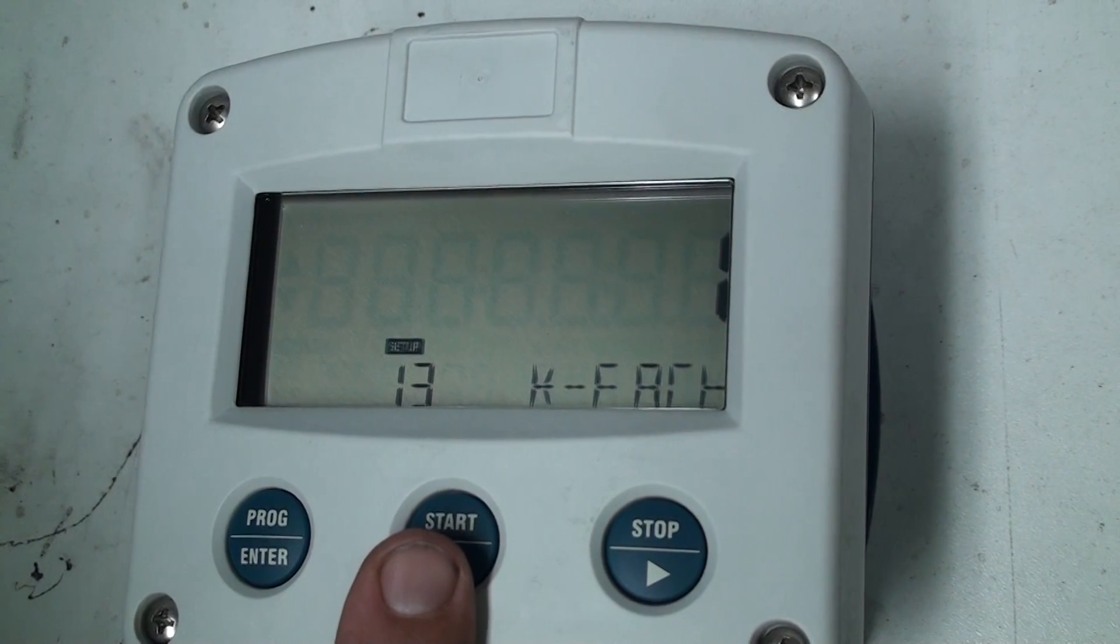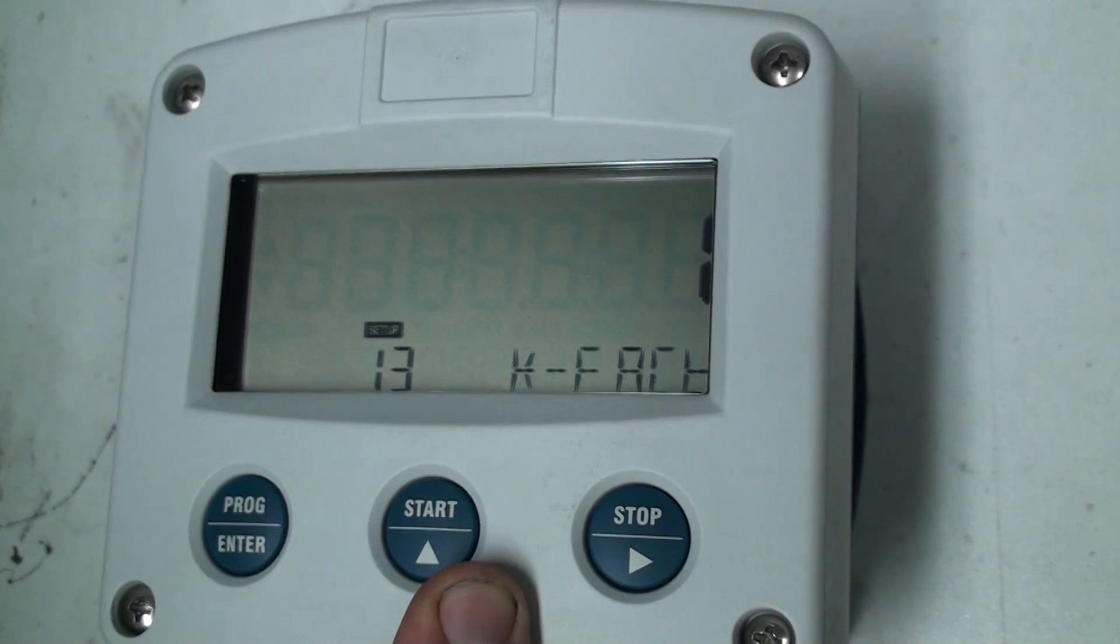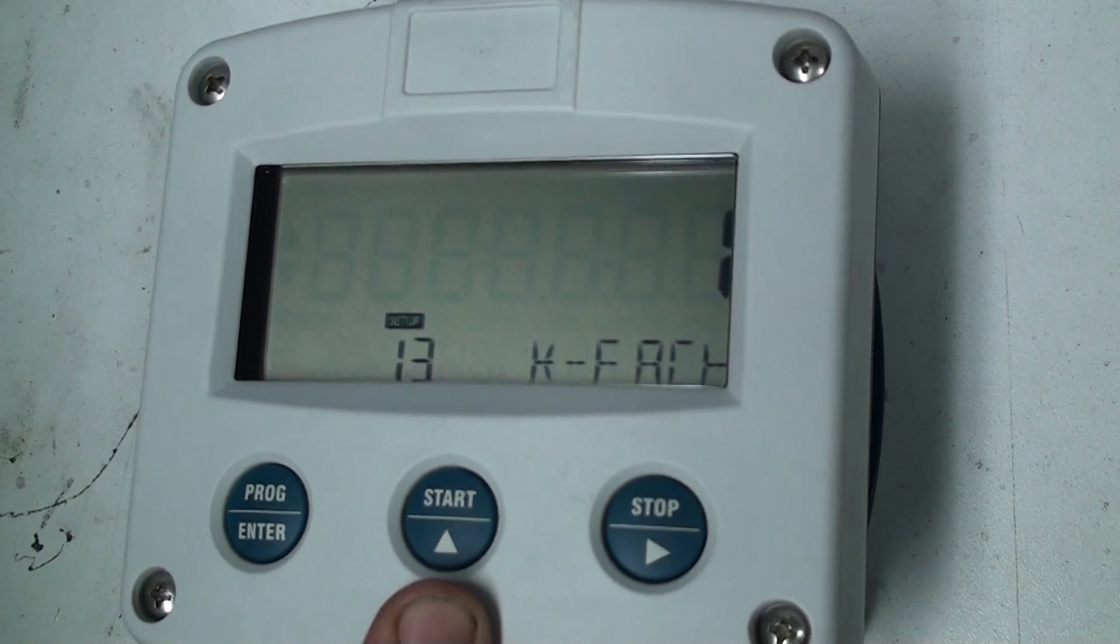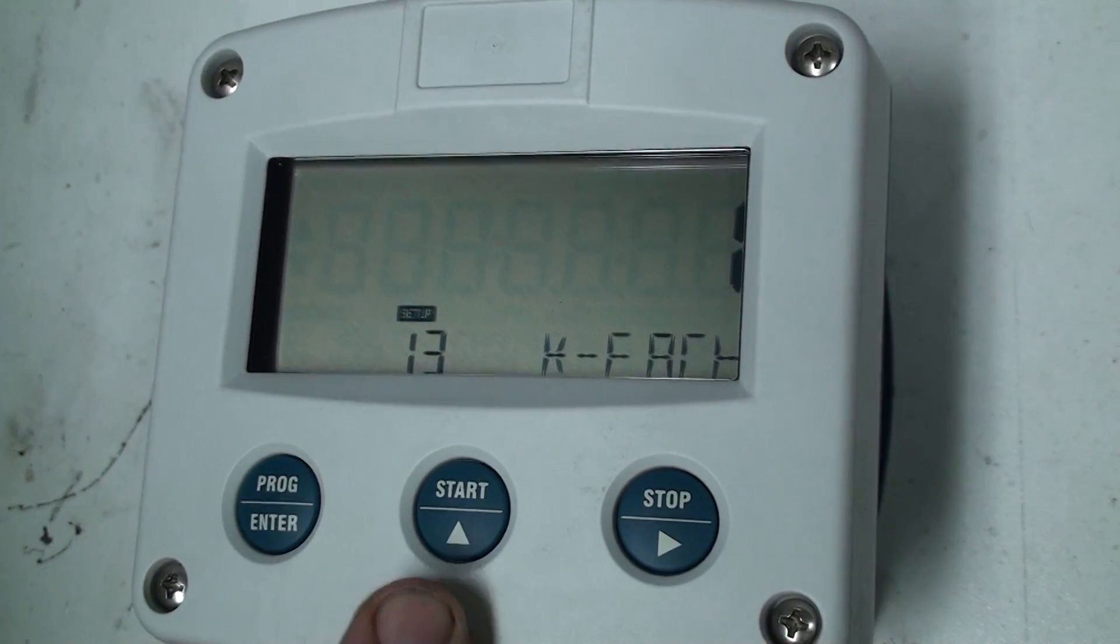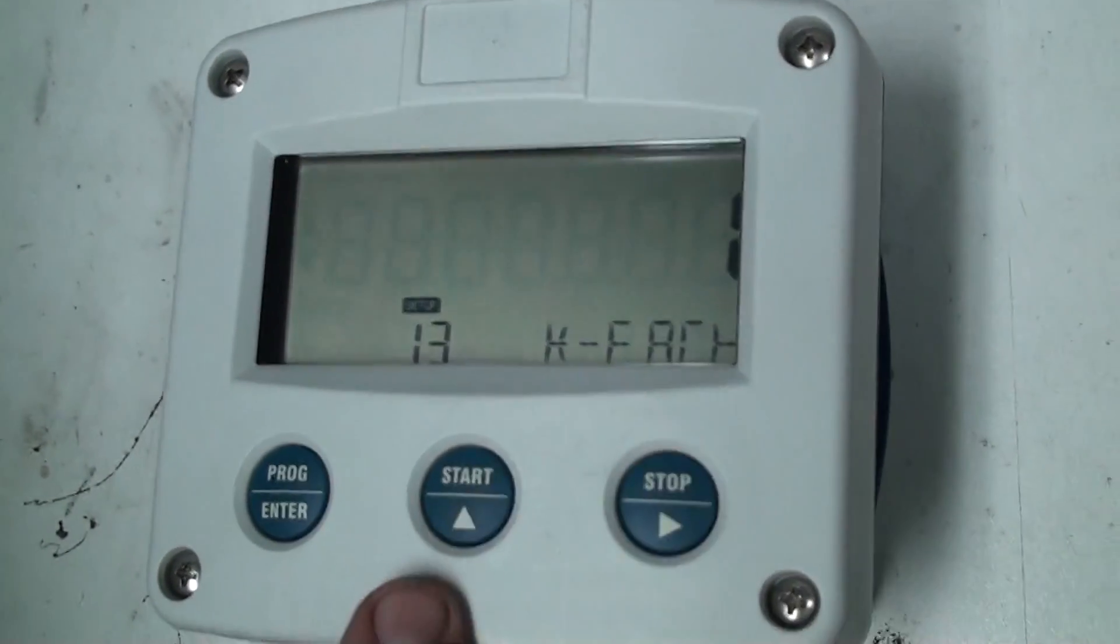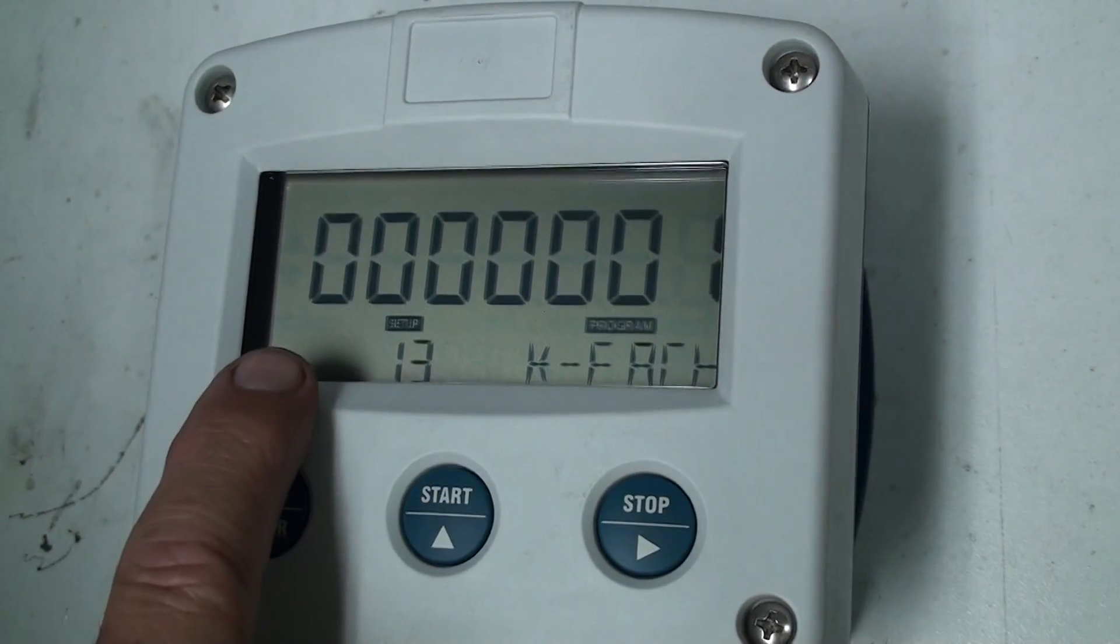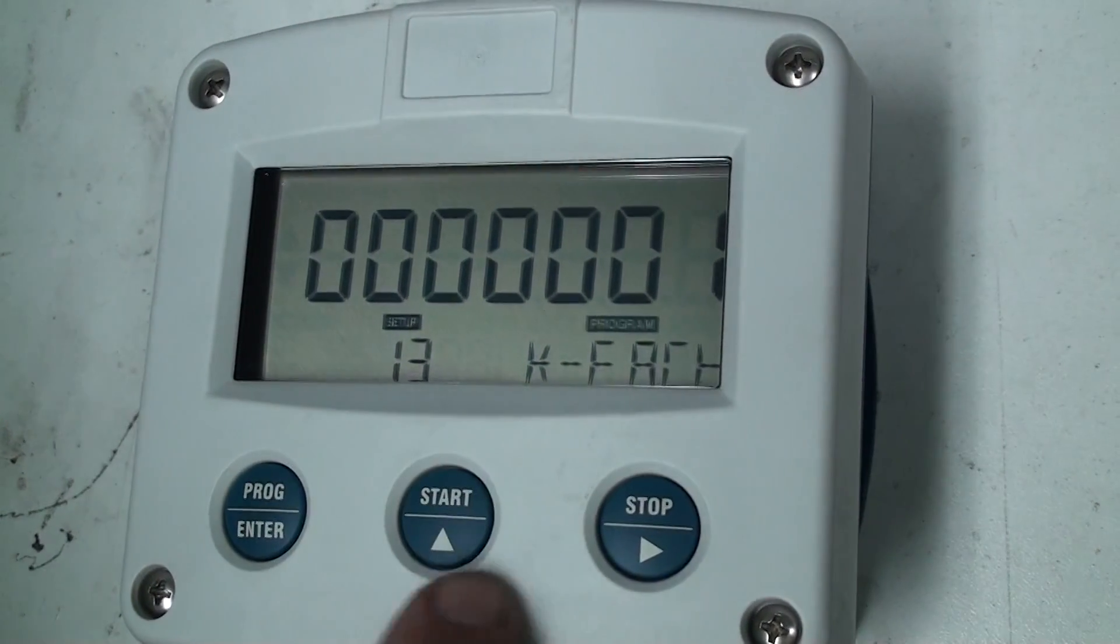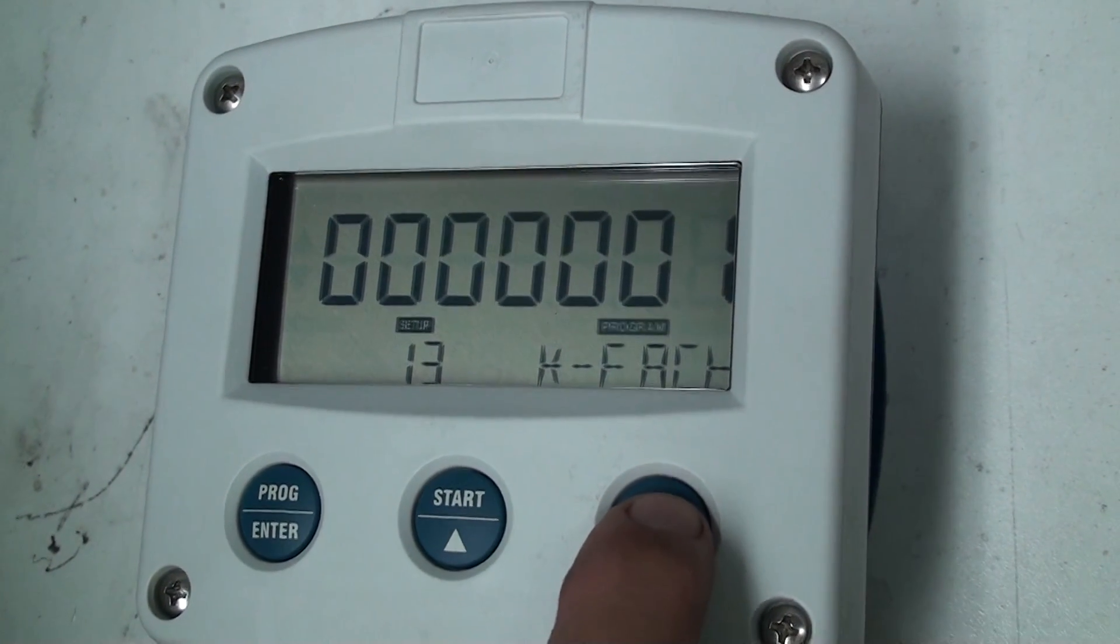1.3 is the k factor and this is set for 1. Now your k factor is your multiplication factor for the amount of pulses per liter that is the output from the flow meter. For our 2 inch meter that will be 6.68. So I need to change this one to read 6.68 and we do that by pressing the program key quickly and you'll see this flashes the left hand digit. The program button flashes and then we move our right button until we get to six.